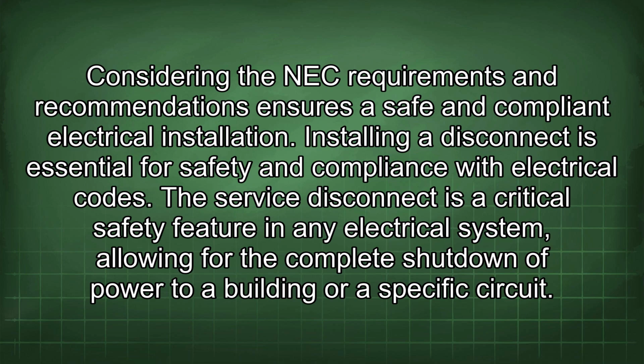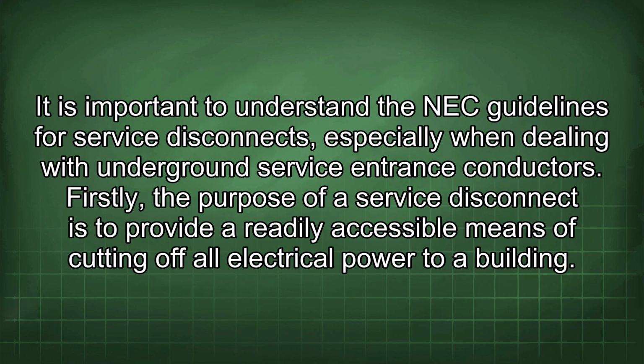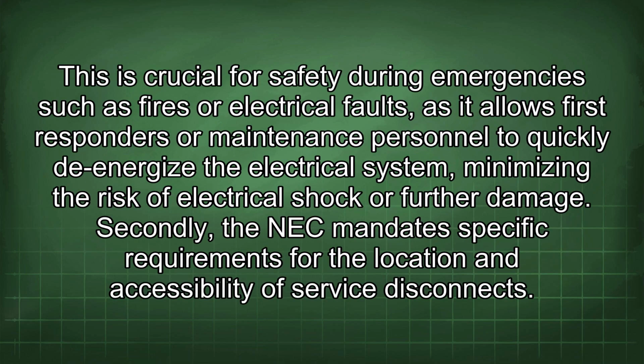The service disconnect is a critical safety feature in any electrical system, allowing for the complete shutdown of power to a building or a specific circuit. It is important to understand the NEC guidelines for service disconnects, especially when dealing with underground service entrance conductors. Firstly, the purpose of a service disconnect is to provide a readily accessible means of cutting off all electrical power to a building. This is crucial for safety during emergencies such as fires or electrical faults, as it allows first responders or maintenance personnel to quickly de-energize the electrical system, minimizing the risk of electrical shock or further damage.